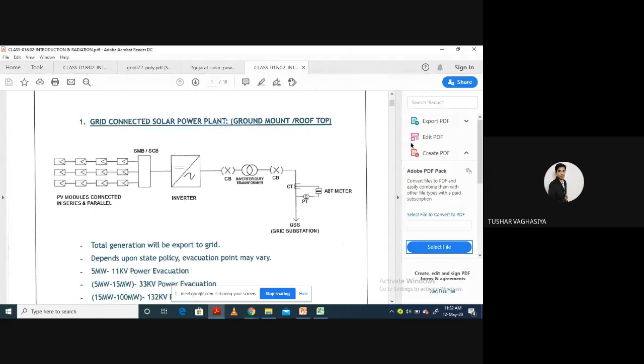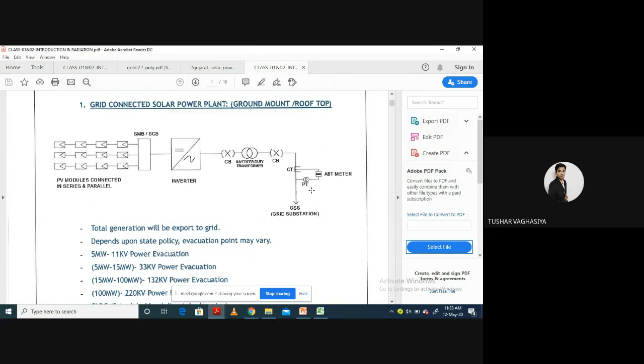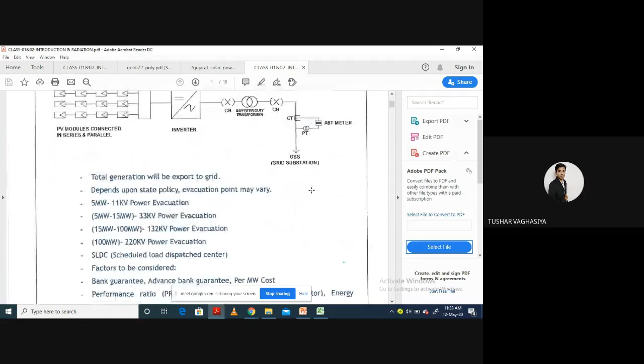If your power plant is more than 1 megawatt, it's mandatory as per the Gujarat policy as well as the Indian government policy to give all the data to the state load dispatch center, because they have to maintain the load schedule as well as the generation schedule. There is also a SCADA system in the solar power plant to monitor the generation. We have to give access to the SCADA system to the SLDC, State Load Dispatch Center, for monitoring our solar power plant if it is more than 1 megawatt, as per the Gujarat policy and Indian policy. This is the utility, or grid connected, solar power plant.